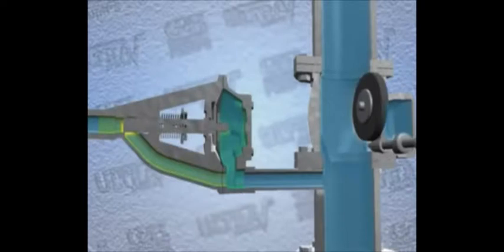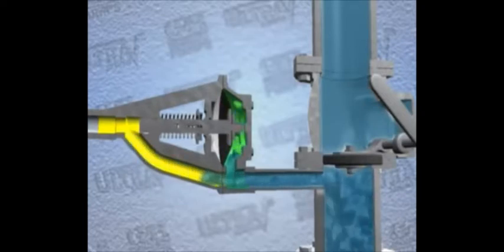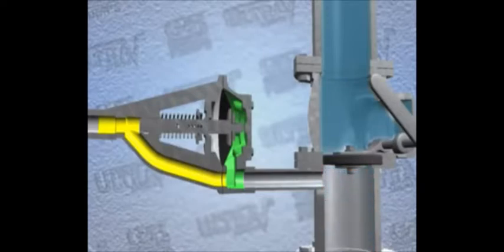At the end of the priming cycle when the pump shuts off, the discharge check valve will close due to static discharge head in the piping, and then the air release valve returns to the open position.